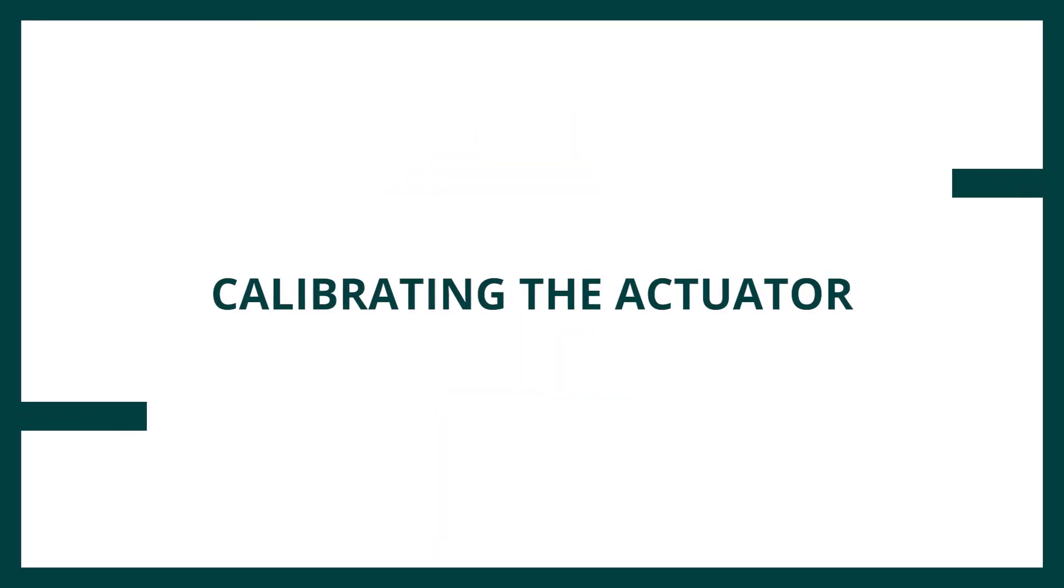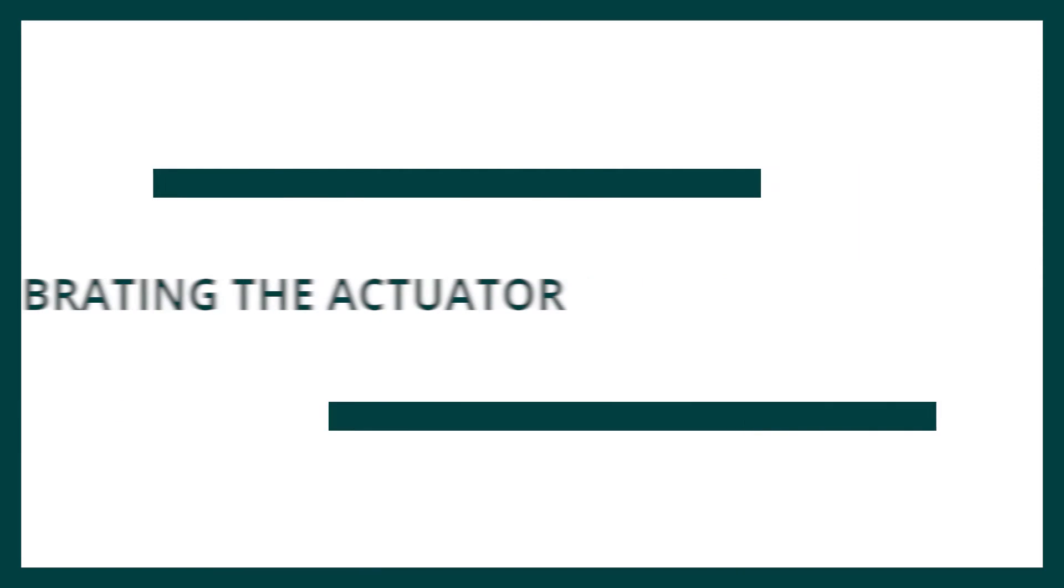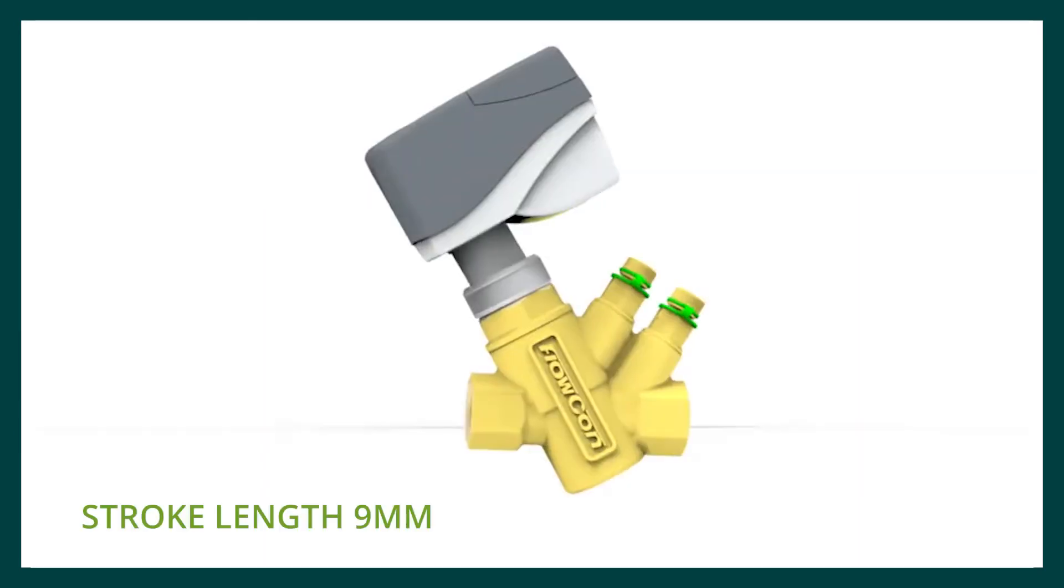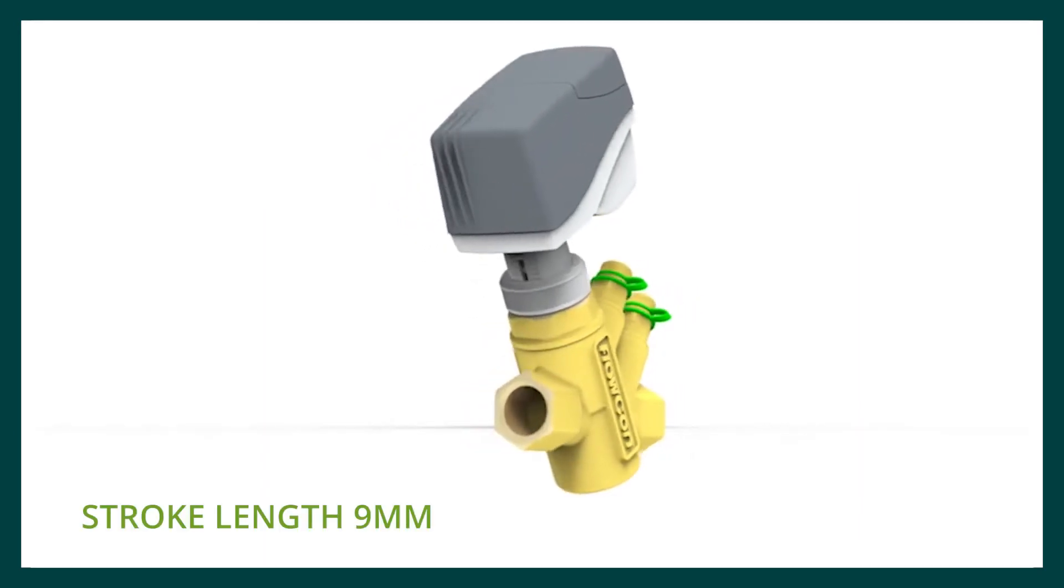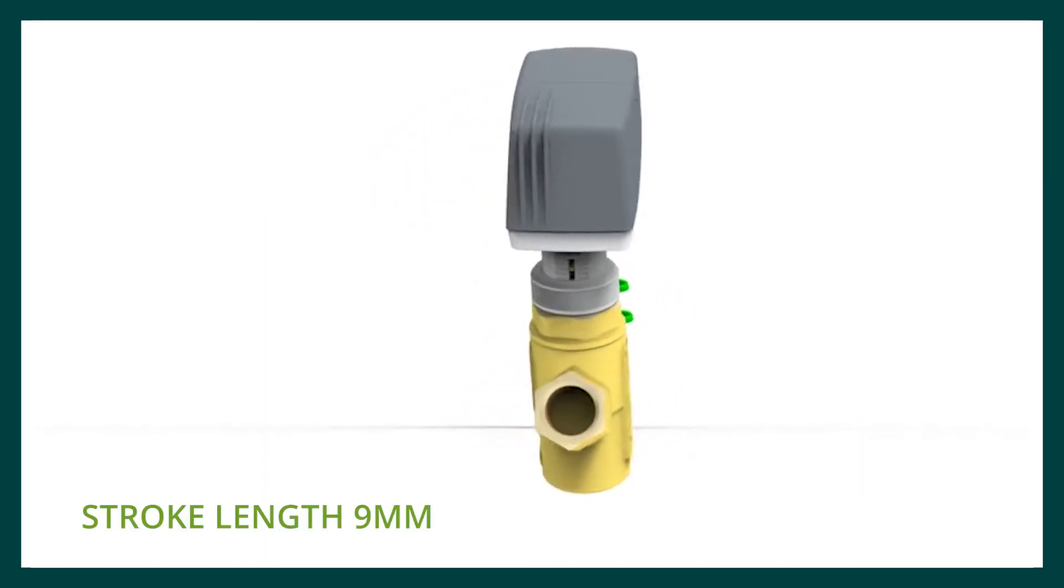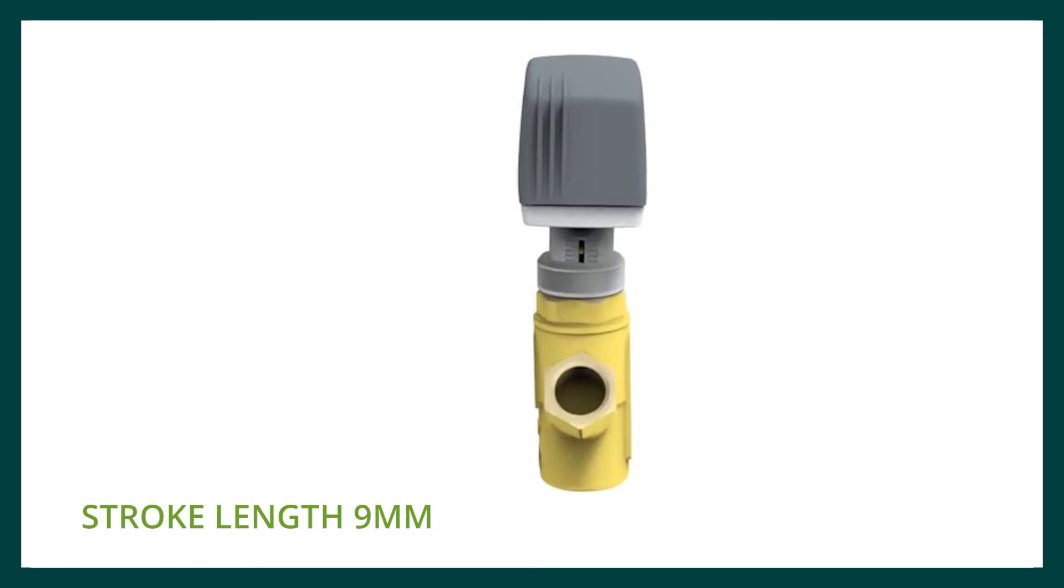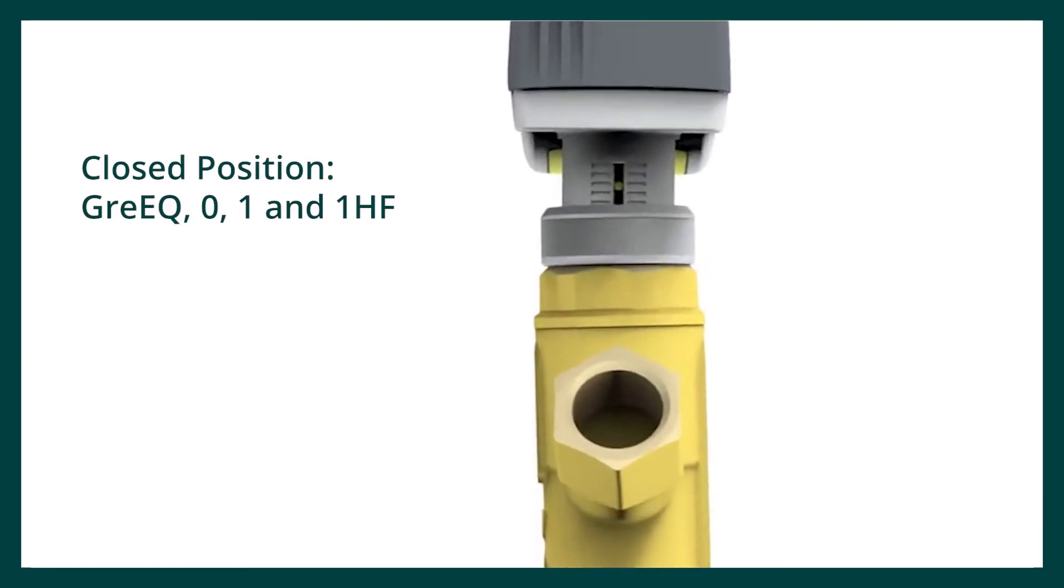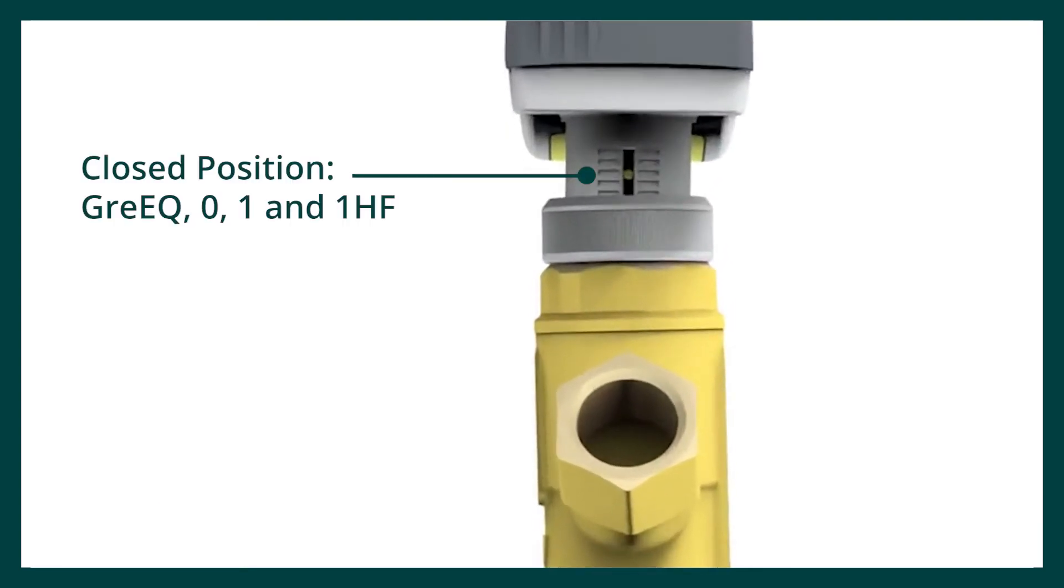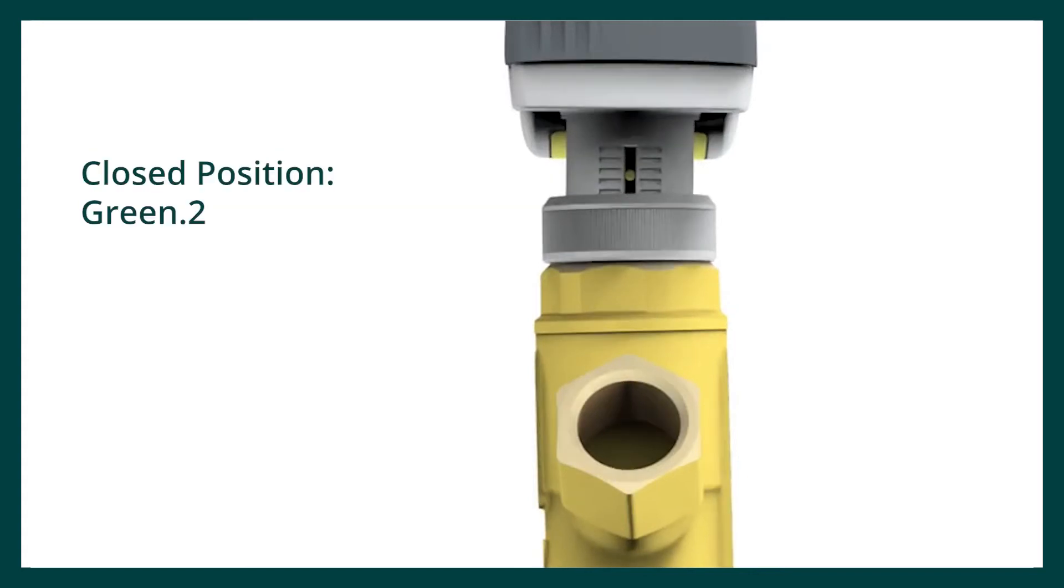The actuator has a stroke length of 9mm and will self-calibrate to the PICV's closed position when the power is turned on. The stainless steel pin located on the actuator neck will indicate when the actuator is fully closed. The closed position is different for the green EQ, 0, 1 and 1HF compared to the Green.2.